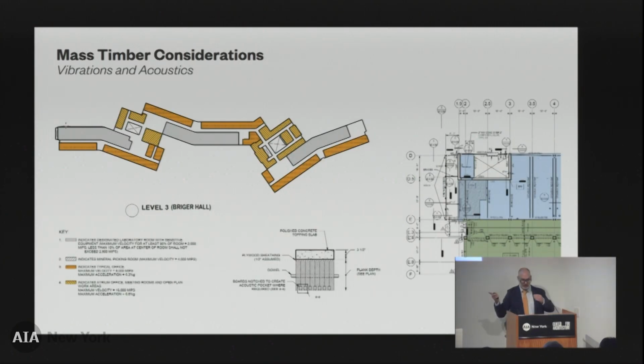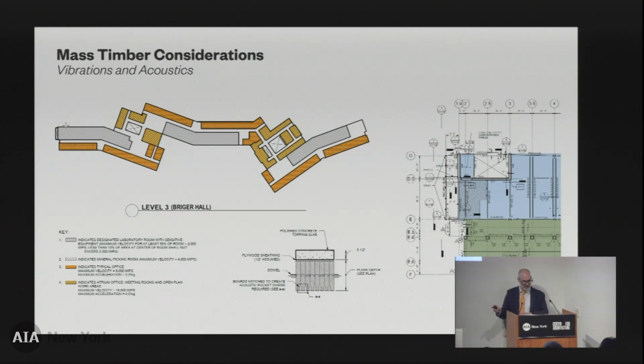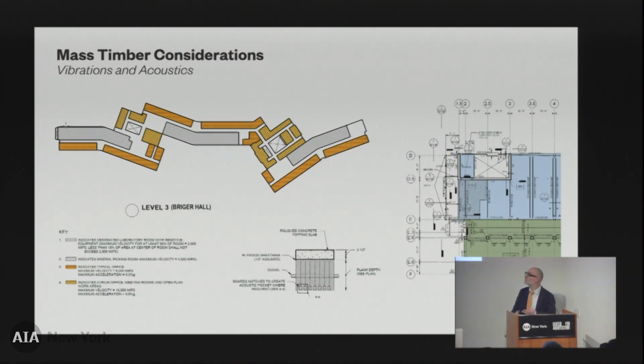Vibrations and acoustics - this is a big one. We talked about steel in the labs; vibration criteria there was 2,000 MIPS or better, in the steel zone. Outside of that, in the darker orange, those office spaces had lowered vibration criteria, and even further lowered in these other areas. That gave us a lot of flexibility on the size of the DLT, spacing of beams, and things like that.